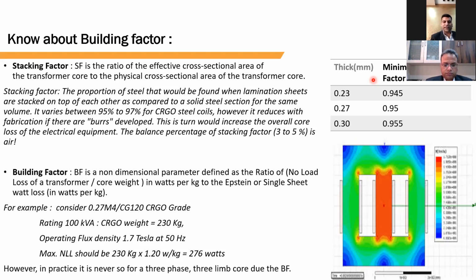Now we are going to understand building factor. Building factor is a non-dimensional parameter defined as the ratio of no load loss of the transformer to the core loss in watts per kg, measured either on Epstein or single sheet tester. To explain building factor, I have given one formula, and the example is here. To derive the no load loss of a transformer core, we should have the design weight of the CRGO, we should have the operating flux density, and we should know the building factor for that particular transformer.